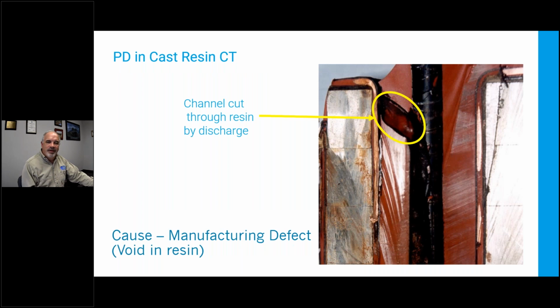Here's an example of internal discharge where it has eaten the hole. So this is a cast resin CT. It's been cut in half, and the conductor here has been removed. But it ate right through that resin. That resin's hard stuff. This may have taken decades, but it cut through it and was on the verge of failure. This would move slower than surface discharge because we don't have the nitrous oxide. All we have is the heat of the spark. And each time that goes, it may kill a couple molecules of insulation, and it takes a while to eat a channel all the way through.